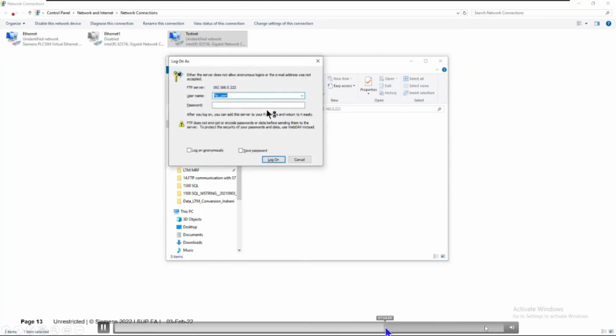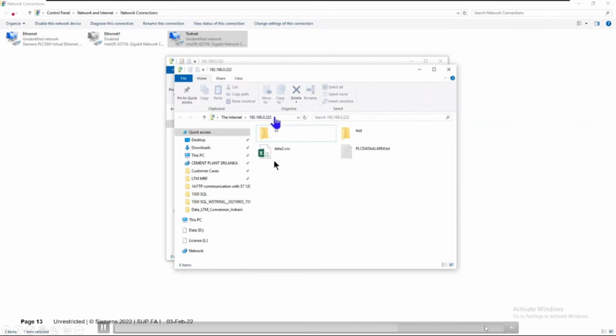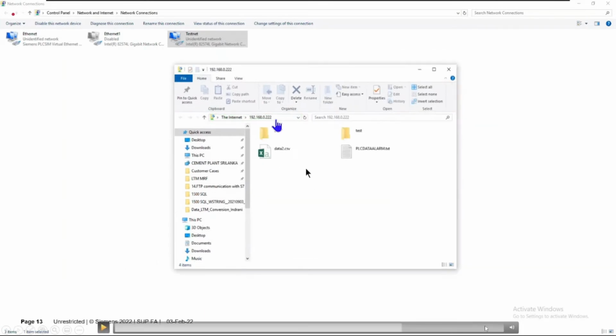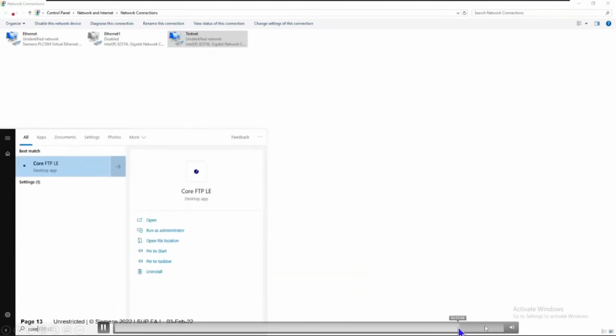Once your settings are done on the FTP side, cross-check with the specific IP address through which your PLC is going to connect. With that IP address, you should be able to access it with the user credentials you created or assigned, and check whether you have both read and write access. Once that is done, we recommend using an external third-party tool also and doing the same thing.